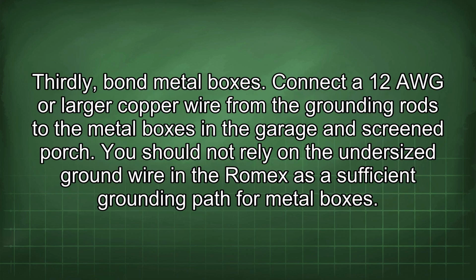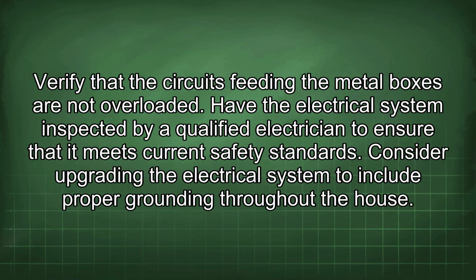Thirdly, bond metal boxes. Connect a 12 AWG or larger copper wire from the grounding rods to the metal boxes in the garage and screen porch. You should not rely on the undersized ground wire in the Romex as a sufficient grounding path for metal boxes. Verify that the circuits feeding the metal boxes are not overloaded. Have the electrical system inspected by a qualified electrician to ensure that it meets current safety standards.